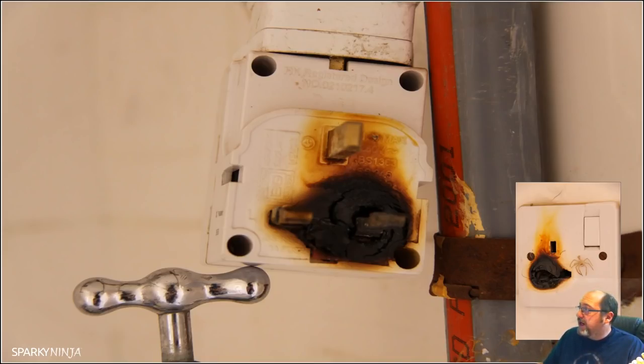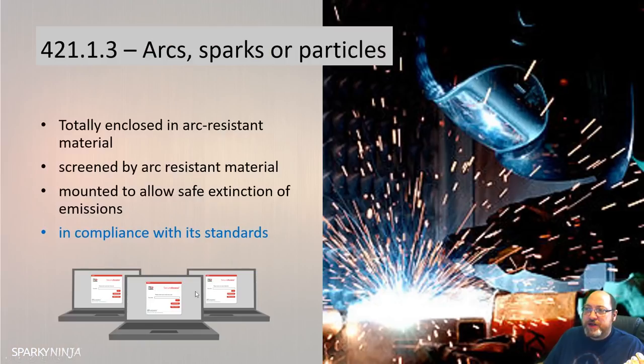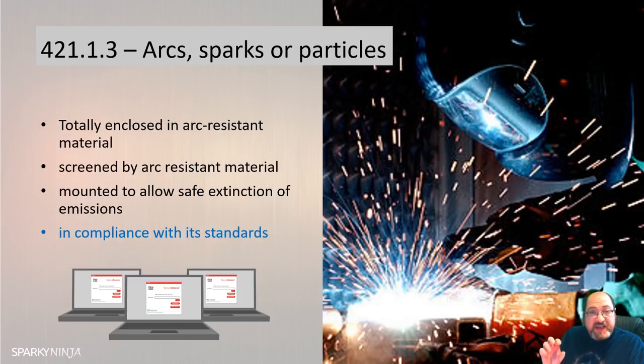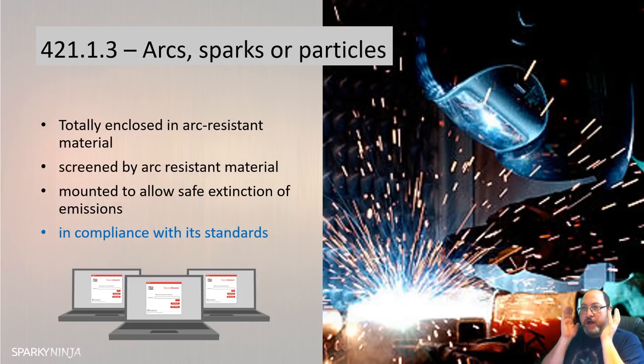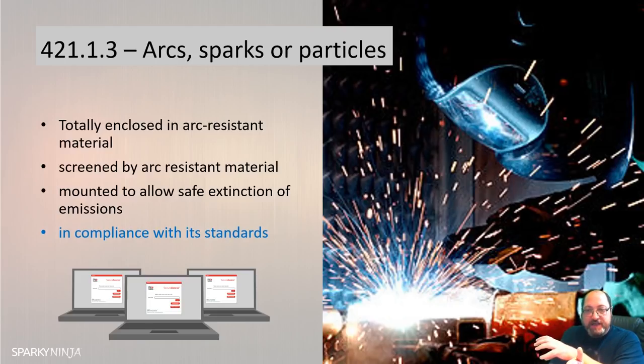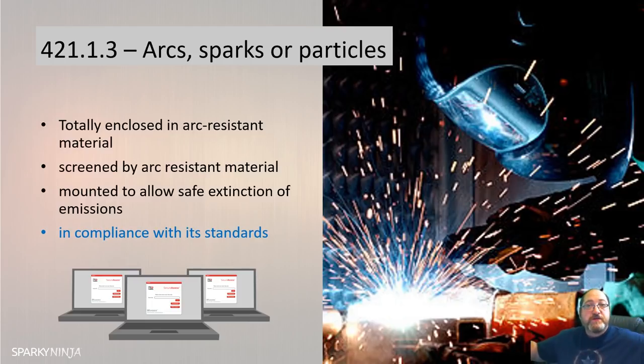Regulation 421.1.3: where arcs, sparks or particles at high temperature could be emitted by fixed equipment in normal service, the equipment shall meet one or more of the following. It will be totally enclosed in an arc-resistant material so the arc and particles can't escape, or screened by resistant material from materials upon which the emissions could have harmful effects, or mounted to allow safe extinction of the emissions at a sufficient distance from combustible materials, or in compliance with the product standard that accommodates this practice.